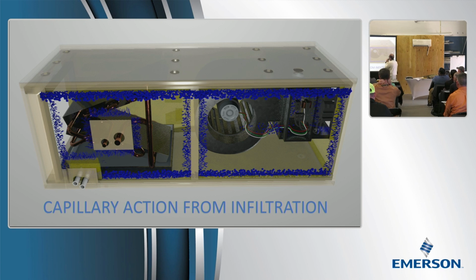But what's going on here is, if you go look, do this. When you go back to work next week, go look in the dumpster at all the stuff the guys tore out. Look at the panel covers. They all have the insulation on them. Where is the mold on the panel cover? Why is it around the doors? Because that's the first condensing surface that molecule got to. We know where it's wet. It's wet all the way around the doors. It's going to be black because things are going to want to live there. And wherever there's an opening, the mold leaves a path to show you where the water is coming in.